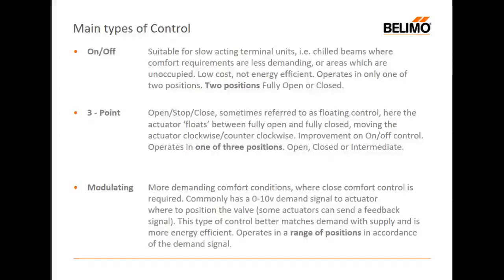And then we look at three-point control, which is a sort of a compromise between modulation and on-off control. And here, and I call this poor man's modulating control, we're sort of doing something in between modulating and on-off. We're moving between open and closed and to an intermediate position. So we're open, or we're closed, or we're moving somewhere in between. And this is often referred to as floating control. So the actuator floats between fully open and fully closed. It's not as efficient as modulating control. It is better than on-off control, but it is a halfway house.